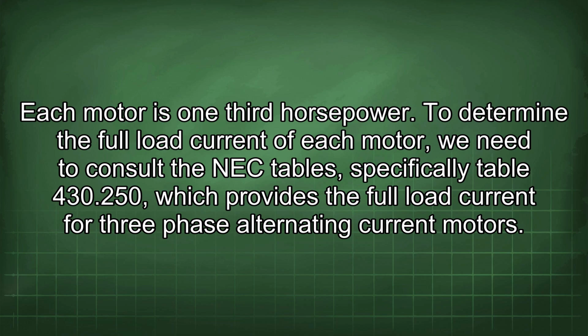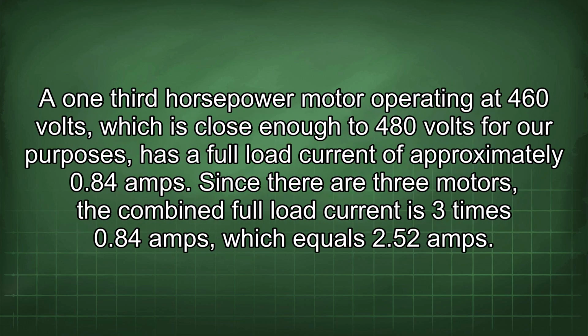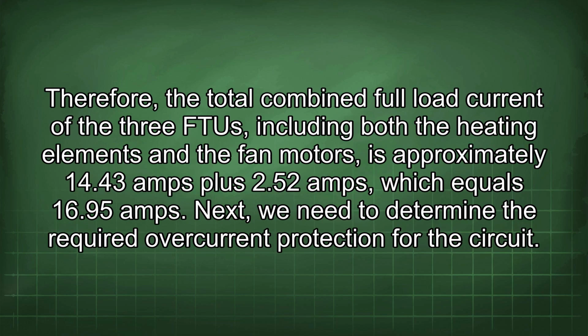Each motor is 1/3 horsepower. To determine the full load current of each motor, we need to consult the NEC tables, specifically Table 430.250, which provides the full load current for 3-phase alternating current motors. A 1/3 horsepower motor operating at 460 volts, which is close enough to 480 volts for our purposes, has a full load current of approximately 0.84 amps. Since there are 3 motors, the combined full load current is 3 times 0.84 amps, which equals 2.52 amps. Therefore, the total combined full load current of the 3 FTUs, including both the heating elements and the fan motors, is approximately 14.43 amps plus 2.52 amps, which equals 16.95 amps.